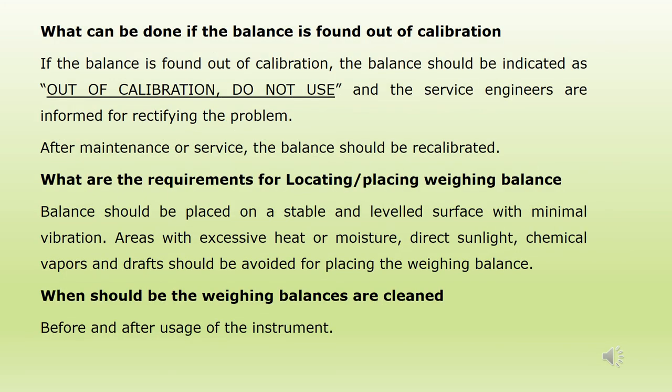What can be done if the balance is found out of calibration? The balance should be identified as out of calibration, must not be used, and the service engineers should be informed for rectifying the problem. After maintenance or service, the balance should be recalibrated.